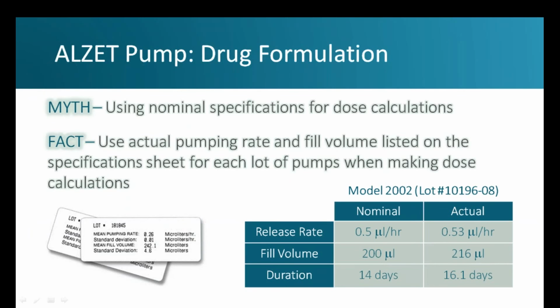When it comes to making calculations about drug concentration, drug dose or pump duration, it is critical to use actual pump specifications rather than the nominal specifications listed on marketing materials, as I mentioned earlier. The nominal performance is only a target for all pumps manufactured. However, individual lots of pump will vary from this target within acceptable limits. The actual pumping rate and fill volume of a particular lot of pumps are listed on the top of the instruction sheet included with each box of pumps.